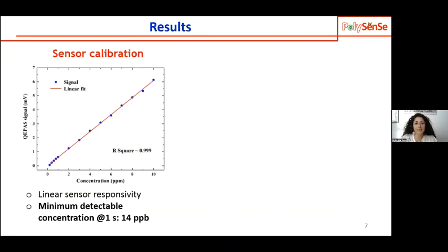We started with the sensor calibration, so we employed a gas cylinder containing a certified concentration of 10 ppm of ammonia in nitrogen, and we verified the linearity of the sensor responsivity with the ammonia concentration in this range, and also we achieved a minimum detection concentration of 14 ppbs using a lock-in integration time of 1 second.